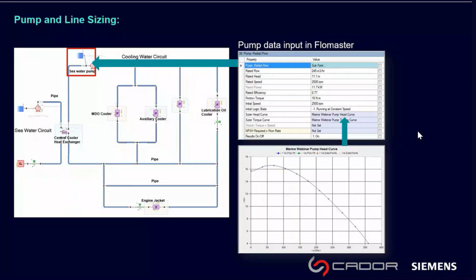To size the pump, you go to the pump component data sheet, shown on the right. You enter things like rated flow, rated head, speed, and so on. Most of this data is available on pump manufacturers' performance data sheets — if you get a performance map from the pump supplier, all that data can be found there and easily entered into the system. You also enter the pump performance curve, which suppliers generally provide, so it's quite easy to input.